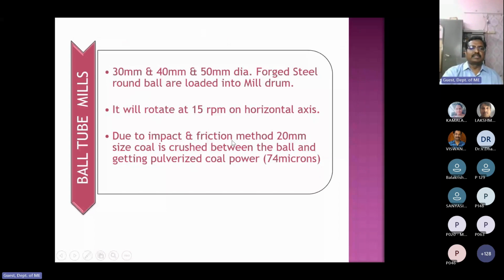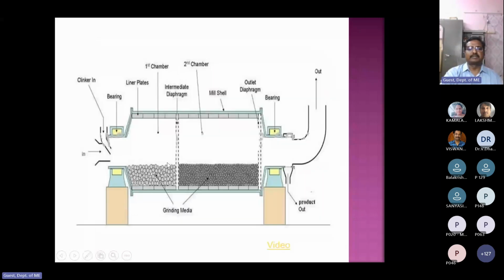Next one is a ball mill. In this ball tube mill, there are three sizes of balls: 30, 40, 50 mm size balls. All are placed in a cylindrical container. The container rotates at 15 rpm about a horizontal axis. Due to this impact and friction method, 20 mm coal particles are crushed into 74 microns. This is the arrangement of the ball mill. These are all the balls.